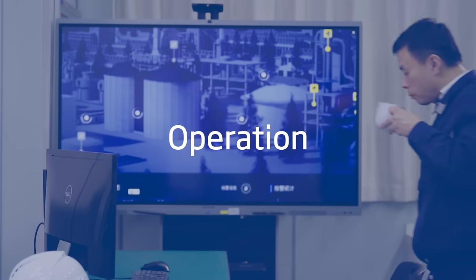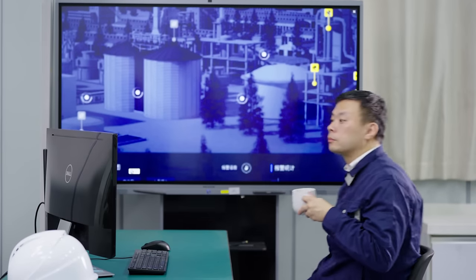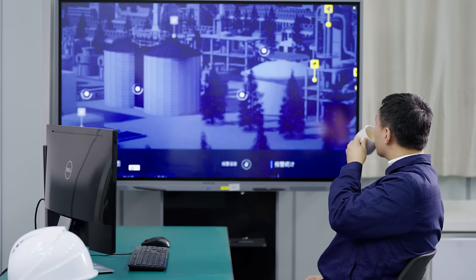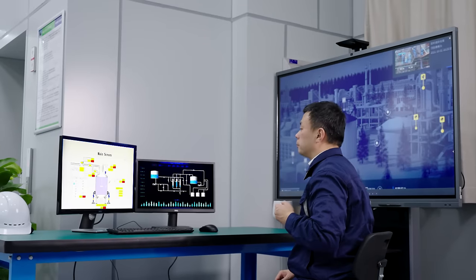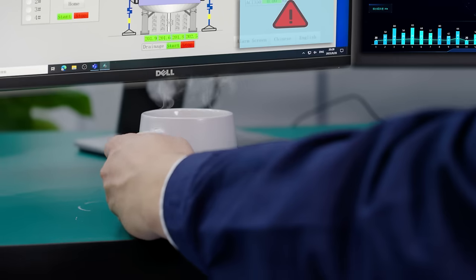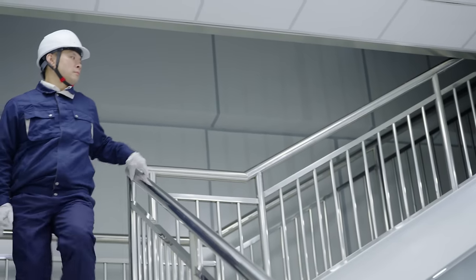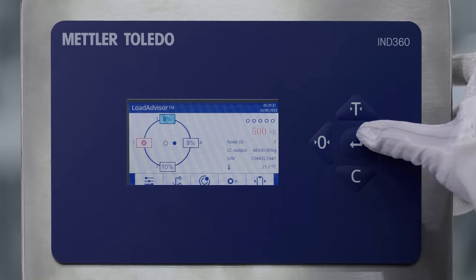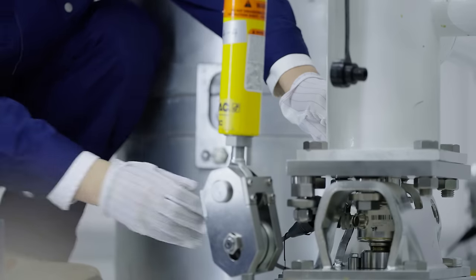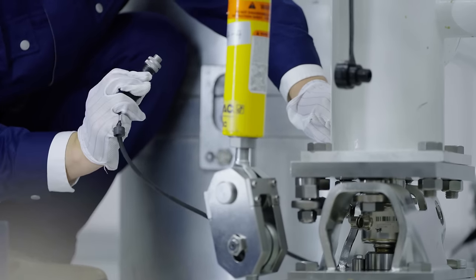During operation, the IND 360 Tank Vessel offers live condition monitoring and alerts you in case of an issue. Alarms are categorized into five levels according to NAMUR NE 107, separating low and high priority alarms. In case of a load cell error, Load Advisor's visualization lets you immediately locate the issue, while Run Flat approximates the weight value to sustain operation while you plan for a fix.